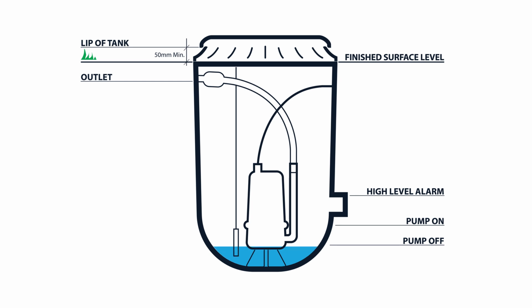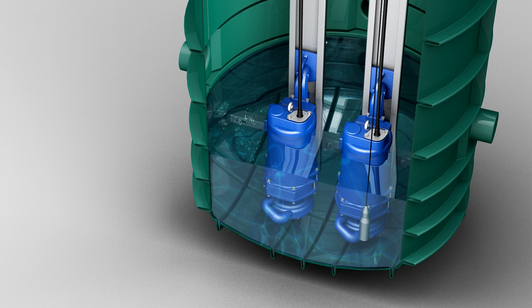Proceed with introducing the water to complete the test. It's good practice to test the system using water. Then you can verify the pump starts at the correct level on the tank, which is just below the inlet. In the case of a dual pump system, we like to do this multiple times so that we can verify the control panel is actually alternating the duty on the pumps.